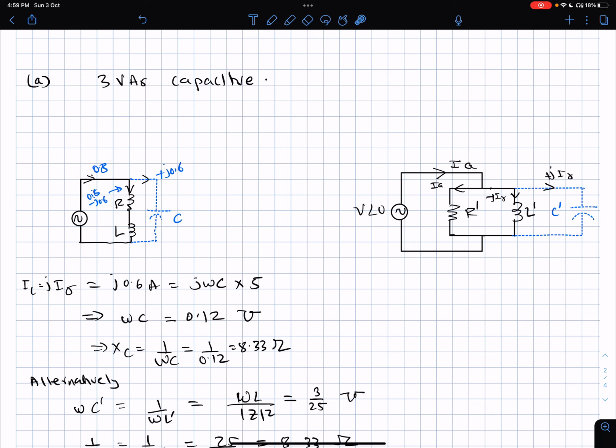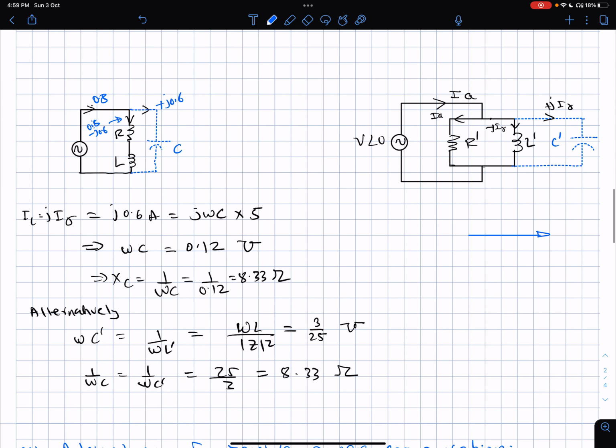So therefore, if the inductive impedance omega L dash and the capacitive impedance 1 by omega C dash are exactly the same, then everything will come out perfect. 100% compensation will be there, and what you would be drawing from the source will be only the active power component of the current, and not at all the reactive power component of the current.